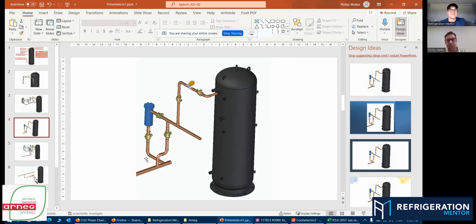So before we move on from the slide, some of the guys might be looking at this. You can see there's a filter here. This is my suction filter. All our machines have a bypass. See, this is why we've got the two ball valves here. We valve off, and then you can easily change your filter cores without shutting down the machine. This is something we do no matter how big or how small, on any type of machine we design. You will not have to pump out the machine. You will not have to turn it off. You can valve off, change your filters, and then keep the machine going.